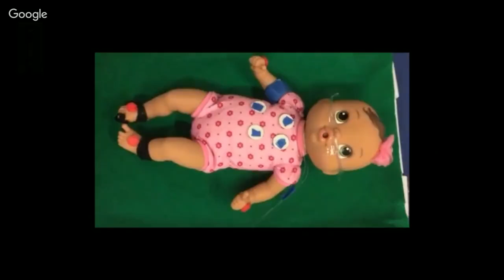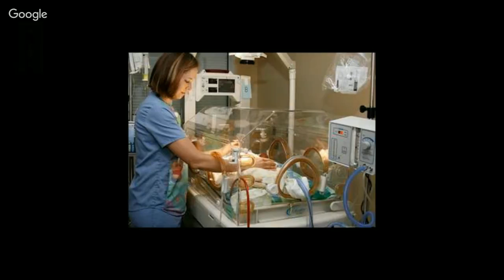When the baby moves, the accelerometer detects movement and transmits data to a Bluetooth-connected device that integrates with the alarm algorithm currently in place. When an infant is being repositioned by a healthcare provider, a button can be pressed near the baby's incubator, which temporarily disables the accelerometers and alarms while the baby is being repositioned and cared for by the nurse. Using accelerometers in conjunction with a button will significantly decrease alarm fatigue and improve quality of care in the NICU.